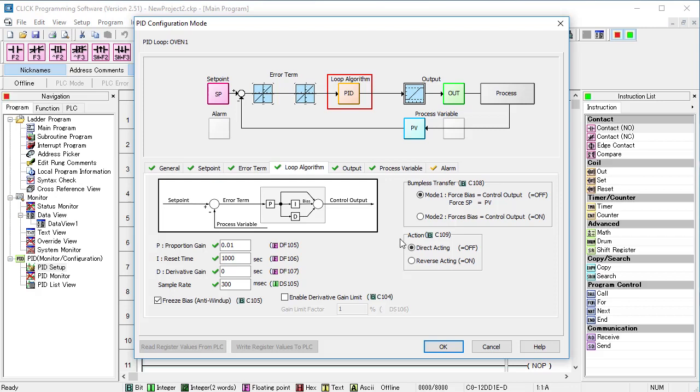So Bumpless mode 1 automatically sets the setpoint to whatever the process variable is, which makes the error 0 so there are no sudden changes in the control output.